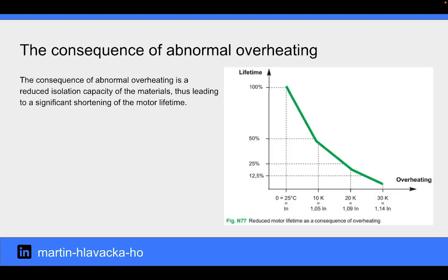The consequence of abnormal overheating is a reduced insulation capacity of the materials, thus leading to a significant shortening of the motor's lifetime. This is illustrated on the graph that justifies the importance of overload or overtemperature protection.